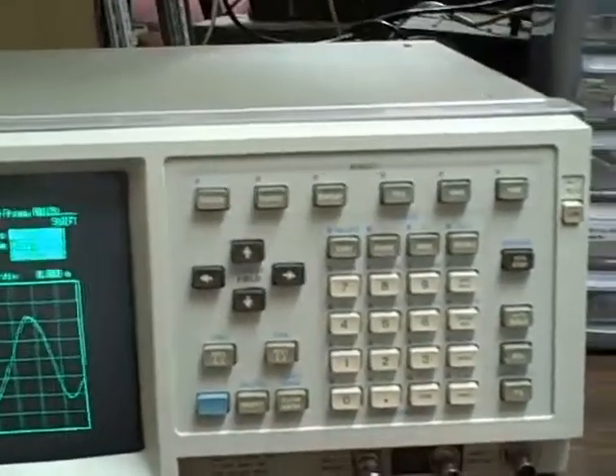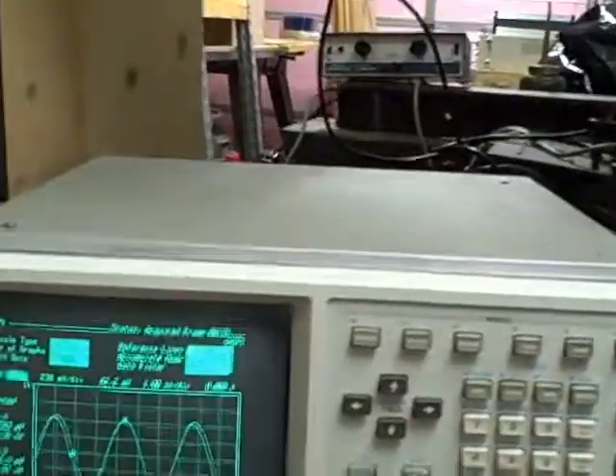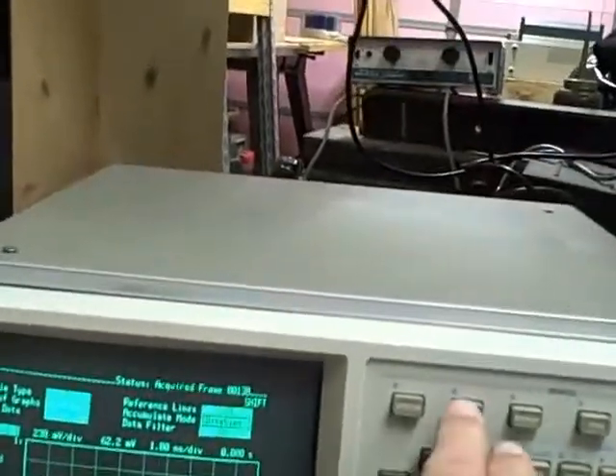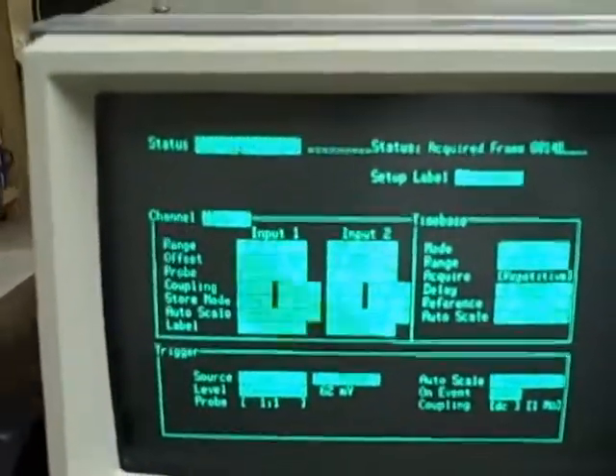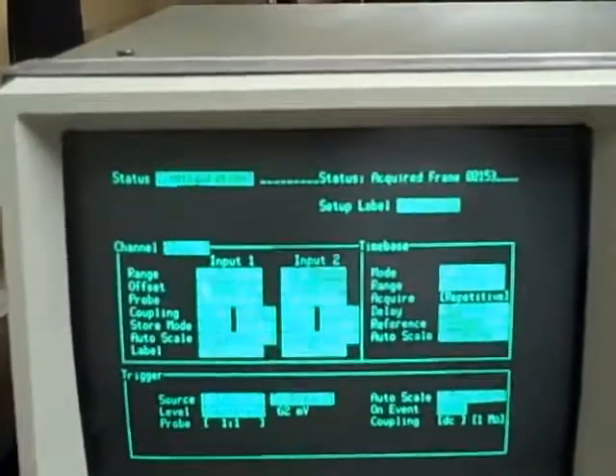You have two inputs plus a separate trigger input, and you have the setup screen which allows you to tell it what kind of probe you're using, how much voltage offset you have, what range you're on, and so on.